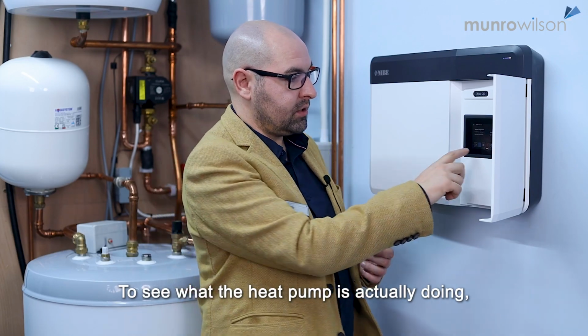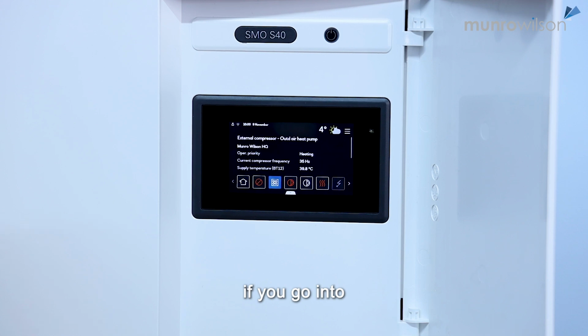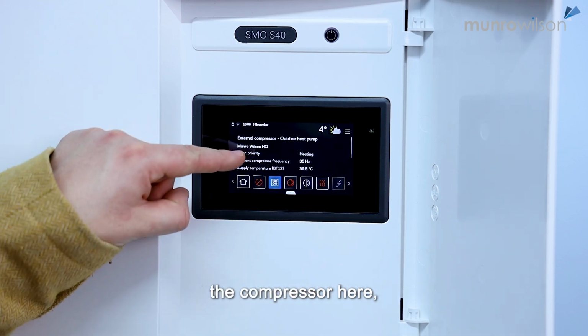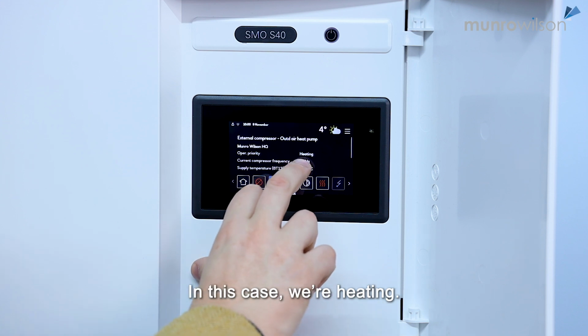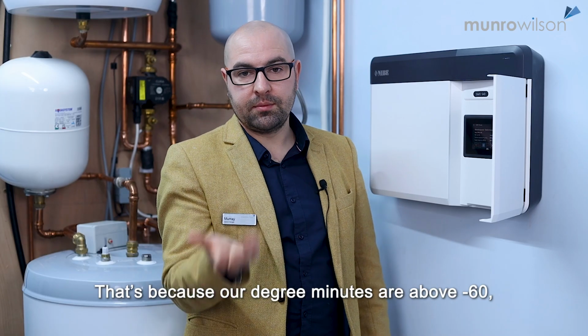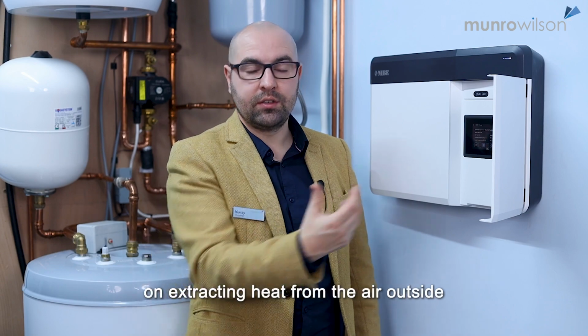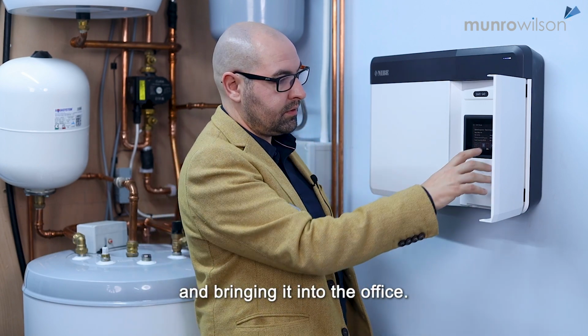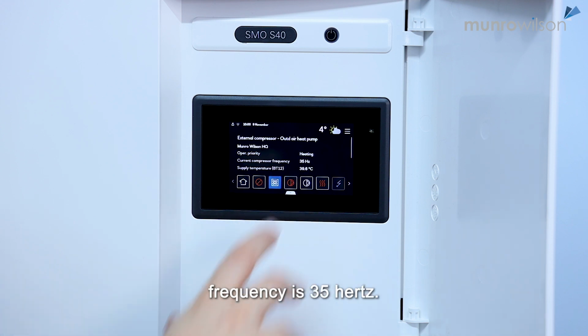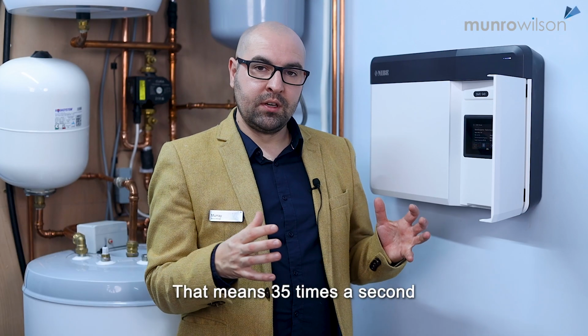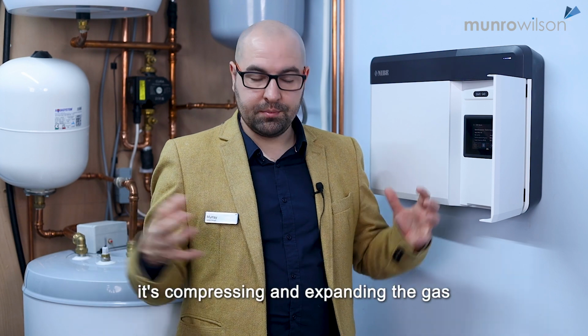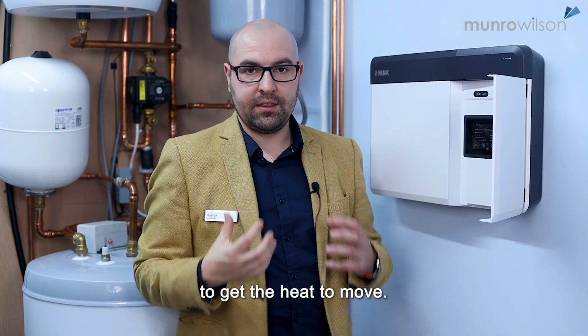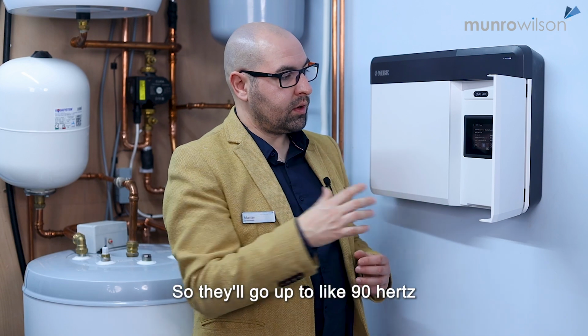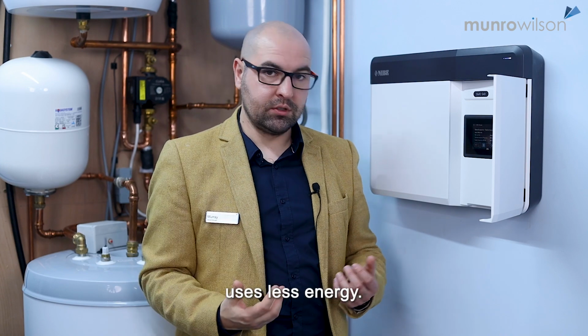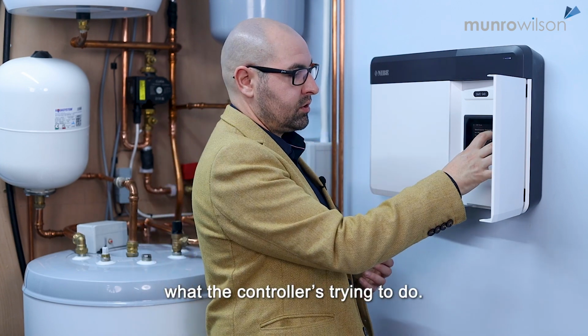So that's a bit about how degree minutes work. To see what the heat pump's actually doing, if you go into the compressor here, it'll say here operating priority. In this case, we're heating. That's because our degree minutes are above -60, so the compressor is actually working on extracting heat from the air outside and bringing it into the office. And our current compressor frequency is 35 Hertz. That means 35 times a second it's compressing and expanding the gas to get the heat to move. They'll go up to 90 Hertz as the heat pump running full tilt, and generally running at lower frequencies uses less energy, and that's what the controller's trying to do.